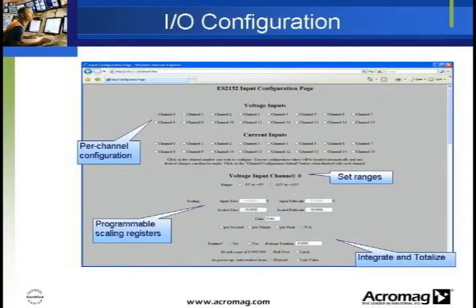Per-channel configuration allows independent customization of each channel's input and output parameters. Each current channel allows the input range to be set at plus or minus 20 milliamps or 4 to 20 milliamps, while each voltage channel allows the input range to be set at plus or minus 5 volts or plus or minus 10 volts. Each channel may also be scaled independently and have integration totalization turned on.